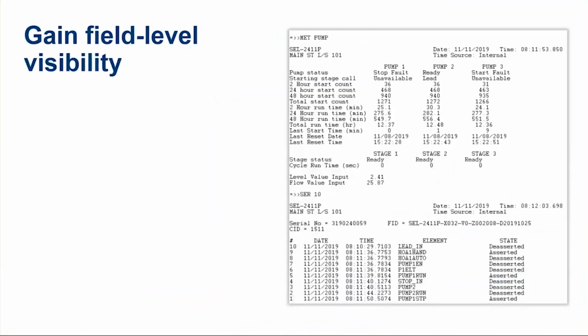Looking at the data in the device through our software, you have a motor report that gives you all kinds of information on the status of the pumps: total run time, last start time, last reset date, total start count, as well as sliding windows of 2, 24, and 48 hour start and run times. All of this information is also available as SCADA points you can bring back to your SCADA system. You can also use this to troubleshoot in the field with a laptop using software, or directly from a remote location if you have engineering access communication to those sites over some kind of communication network.